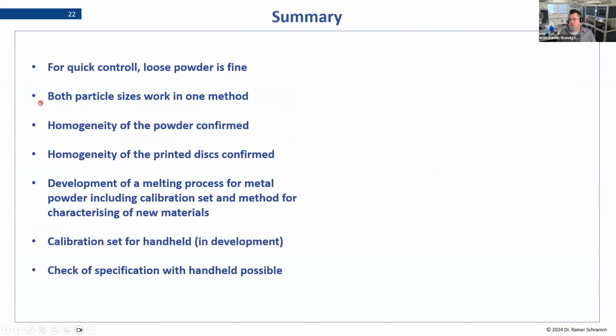The particle size in the powder does not really play a huge effect from what we saw in our tests, which is a surprise because that's quite unusual for XRF. But in this analytical circumstance, and because it's a very homogeneous powder, the particle size effects are not really observable. They don't really play a role. We can ignore them, and we can use the same application for both of these powders, the one for the laser beam and the one for the electron beam, even though they have different particle sizes. We can say for sure that the powders, the 4 examples we had, were very homogeneous, and also the part that we were printing in the end, the result of the printing, was also very homogeneous.